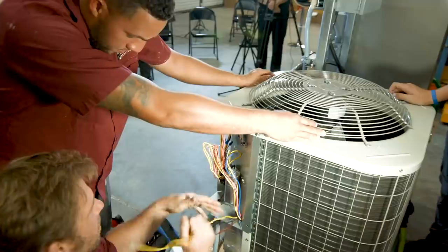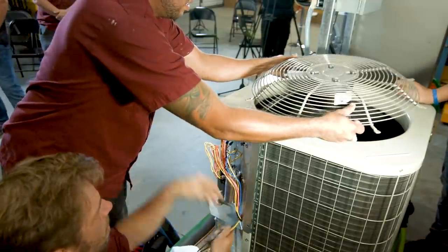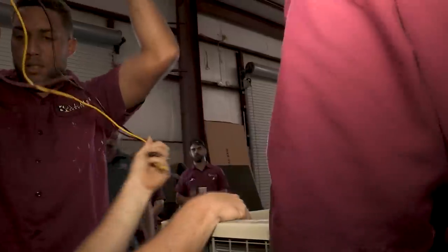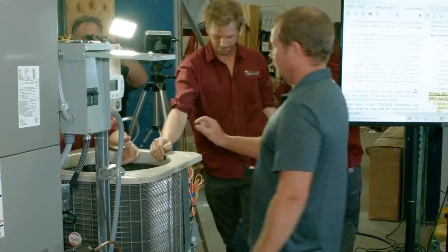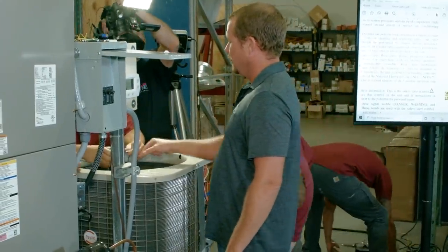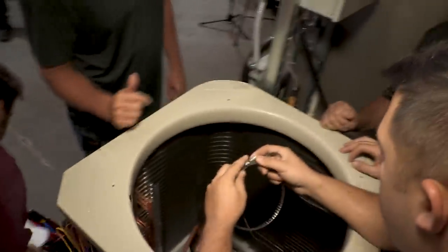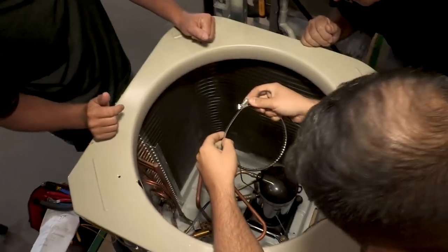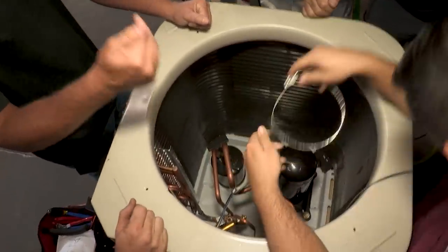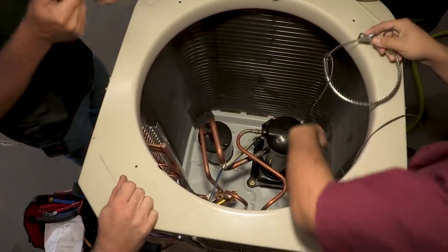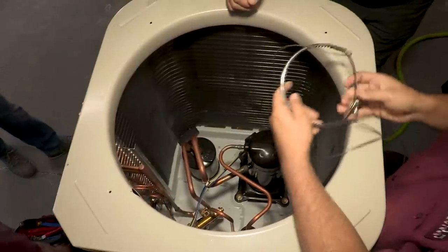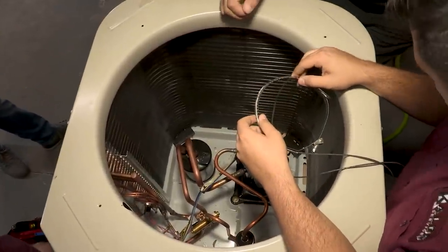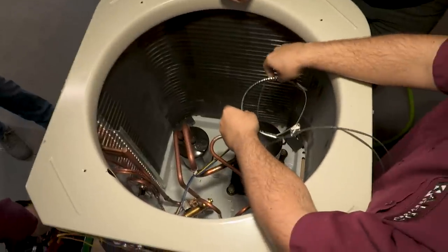All right, so one thing that I want to note quickly on the crankcase heater: the connector on the crankcase heater, the place that you actually make the connection, you want to place that over the seam on the compressor. So if you're mounting that around the base and there is a seam anywhere on the compressor, it's right here. You don't want the heater element portion to be on the seam. You want the place that you tighten the band to be around the seam. Does that make sense?